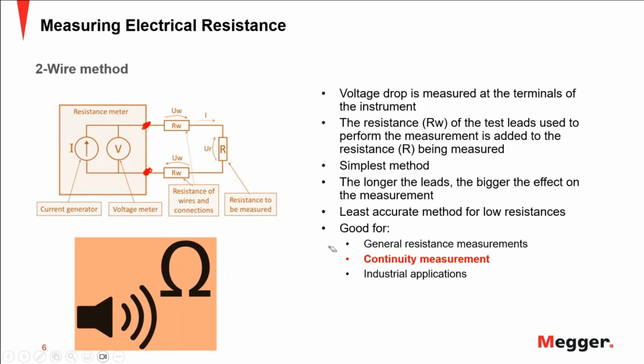For continuity verification, or for industrial applications, it's a very good method, and this is what you typically see in the digital multimeters. You see a symbol of resistance, and you also see the buzzer symbol, because you can get a value of resistance, but just with a beep you can determine whether you have continuity or not. However, because of the voltage and the current that is used for this measurement, you're not going to have the most accurate value, and we're going to see an example of that.